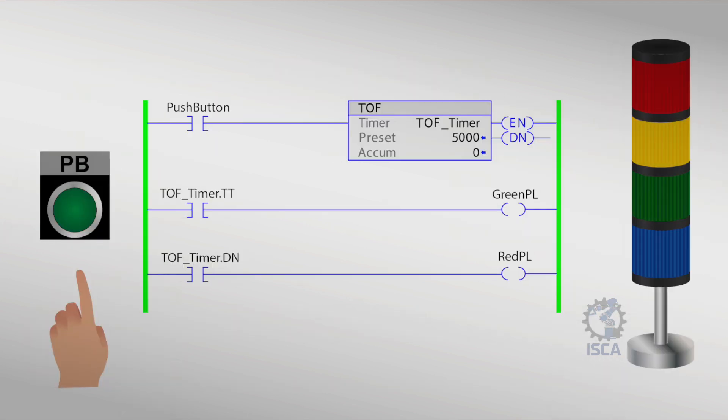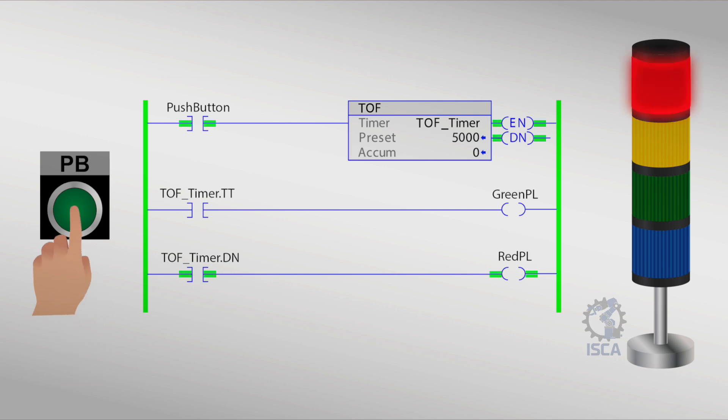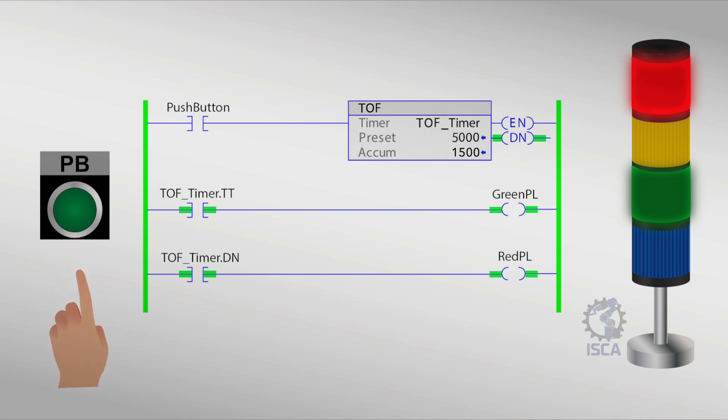The TOF timer is a programming instruction used to switch off the output or application after a certain amount of time. When the input turns on, the done bit, DN, immediately goes true and therefore, the output turns on at the same time as the input. If the input goes low or turns off, the timing process starts and the output will turn off when the timer reaches the set time.